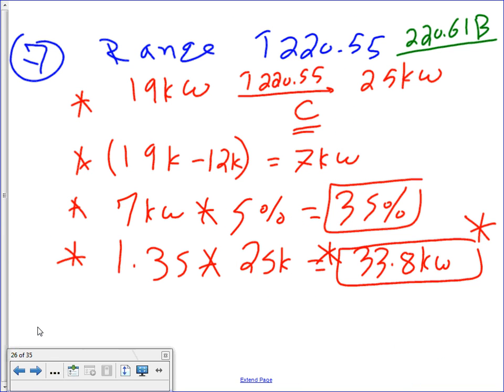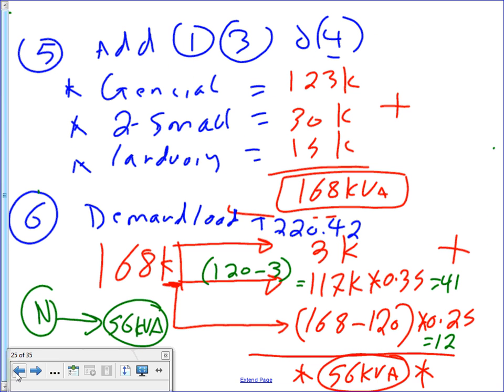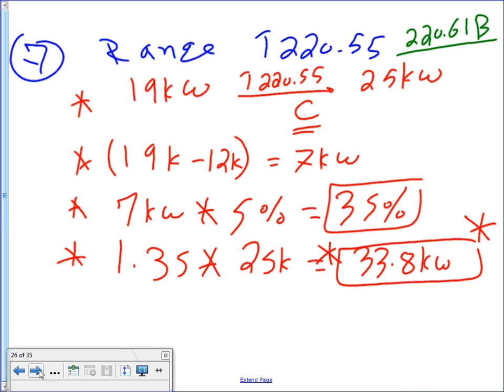Same thing. Let's go to step number 7. Step number 7, that's where the neutral starts differing. Was the last one you did the grounded conductor? Yeah, we're trying to size the grounded conductor with the same neutral. So for all the steps up to 6, it's going to count exactly the same calculation, so you don't need to repeat it. 56. Okay, let's go to 7.